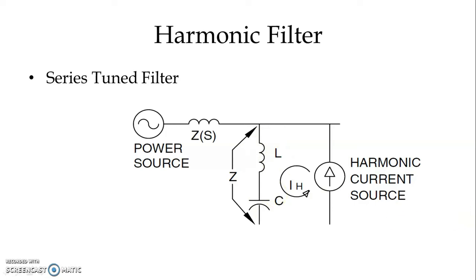This way we can eliminate or filter any frequency of harmonic current. If we require other harmonic frequencies to be filtered out, we can connect different series tuned filters in parallel with each other, and then we can eliminate harmonic currents of other frequencies as well.